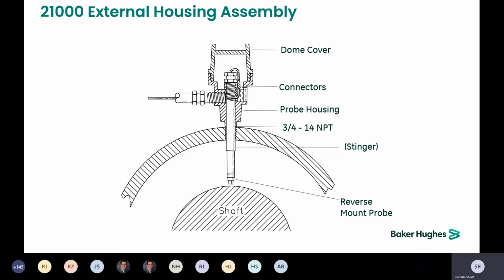So the next method is the external mounting, where the probe is basically mounted through the casing using a housing. Generally, it's a 3/4 pipe thread that is cut into the machine case. This portion here is the lower housing. This is a stinger that goes through. The probe in the stinger is replaceable. It's just a reverse mount probe. And you've got about 2 inches of thread in here to gap the probe.